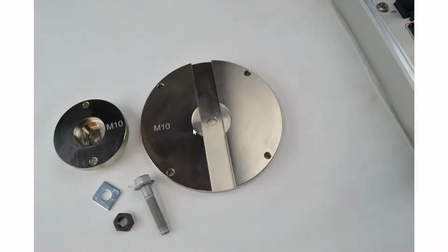For using the load cell, we also need plates. These are M10 plates and bushings. The head part goes to the plate, and the bolt and nut part goes into the bushing. The nut part slides and fits in this section, so it stops it from rotating. We also use a square washer in this section to save the plate from wearing off. Also, it gives you the constant friction surface between the bolt and the surface of this square washer.